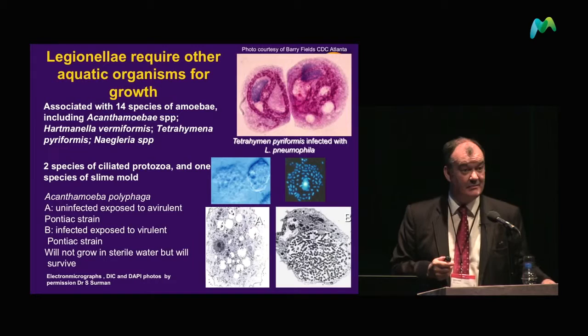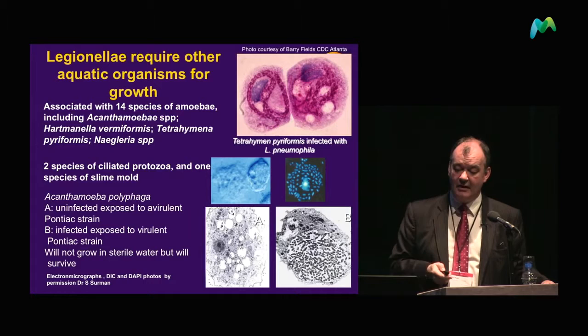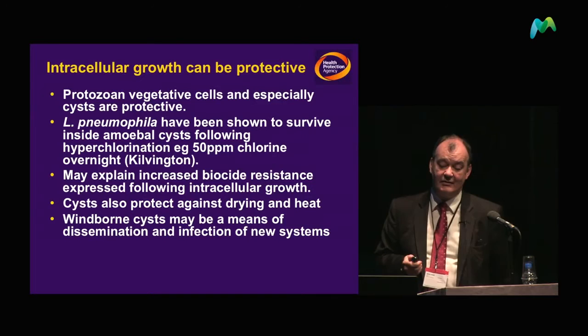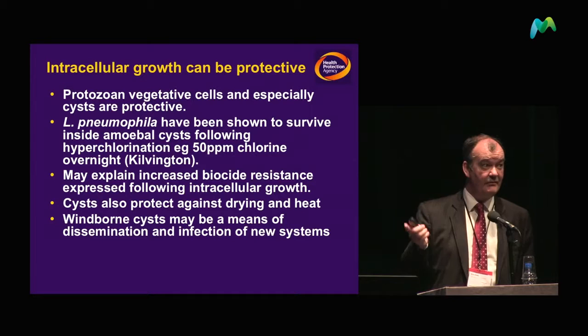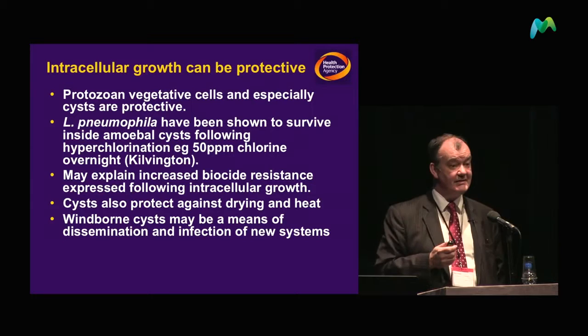These are some of the organisms in which Legionella lives. An enormous number of amoeba can support Legionella, and living within a protozoal organism is actually very protective. This is quite a challenge when trying to treat systems that are already contaminated, because Legionella can survive up to 50 parts per million of chlorine inside some of these organisms.